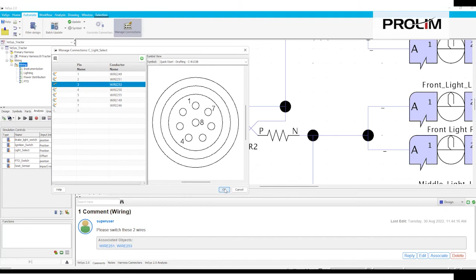So I'll hit OK here, and again, because this simulation is always working in the background, anytime I make a change and go back in, you'll see here quickly that the analysis automatically updates in the background and gives me real-time feedback of how changes are affecting the flow of the power. So now that I made the change, according to the designer's note, position 4 should be front and warning lights. Looks like we've got power to the front and warning lights.